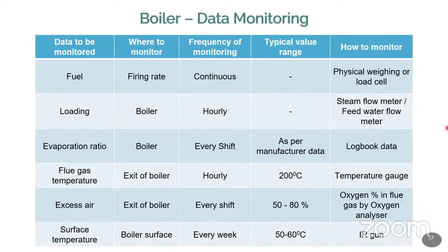Now, what is the data to be maintained? For condition monitoring of the boiler, you have to do it regularly. So you need to monitor the fuel rate and the loading percentage of the boiler, evaporation ratio, flue gas temperature, and how much excess air you are passing to the chamber, normal air plus excess air. Excess air must always be passed, so you need an oxygen value. We have only 21 or 22% oxygen in the atmospheric air. So you require more air to be passed to the chamber so that the required amount of oxygen can be taken.